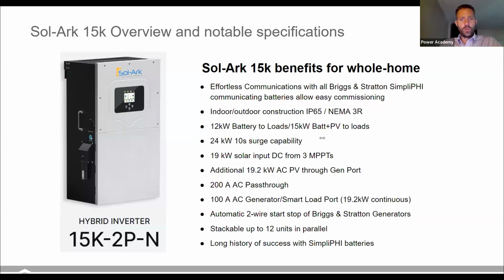You've got an additional 19.2 kilowatts of AC PV through the gen port if that port remains open. Big thing for me, that 200 amp pass through makes this easy to install. You've got a 100 amp breaker on the generator port. For continuous use, you'll want to derate down to 80 amps continuous. You've got automatic 2-wire starts of all of our Briggs & Stratton generators. And you can stack this unit up to 12.